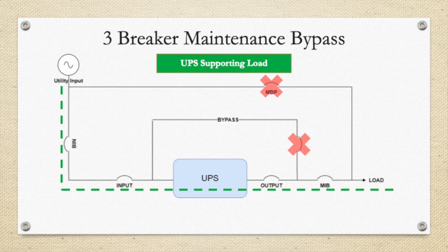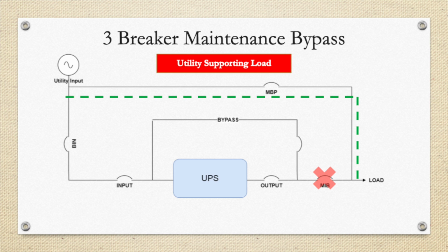So in this configuration, we must make sure that we transfer the UPS to internal bypass before we attempt to go to maintenance bypass. On the next drawing, we're showing that 3-breaker maintenance bypass configuration running in the maintenance bypass mode. So therefore, BIN, the utility input to the UPS, and MIB, the output isolation of the UPS, can both be open, and the maintenance bypass will be supporting the load.